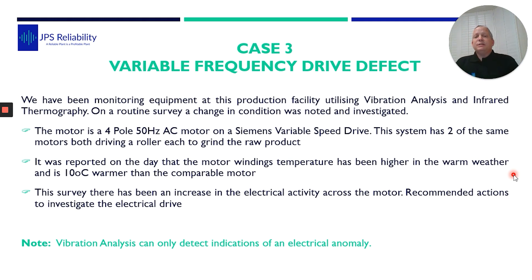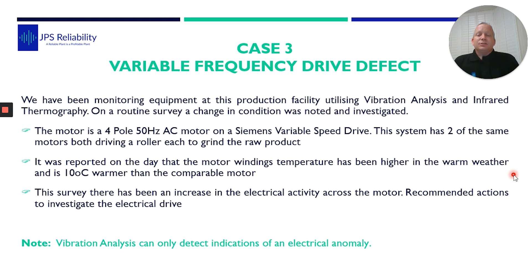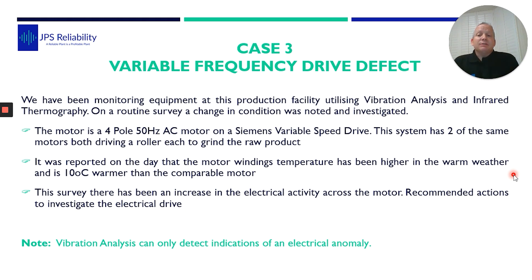A bit about the history: this is a routine site we go to regularly — electrical thermography on a gin, a bit of mechanical thermal survey, mainly vibration analysis on the mechanical plant. On the routine survey, we noticed a change in the vibration pattern — not necessarily amplitude, but a distinct change in the pattern. So we used thermography to check out the motor. Usually there is a temperature difference as the seasons change, but on this day we actually saw a 10-degree difference in the motor stator.